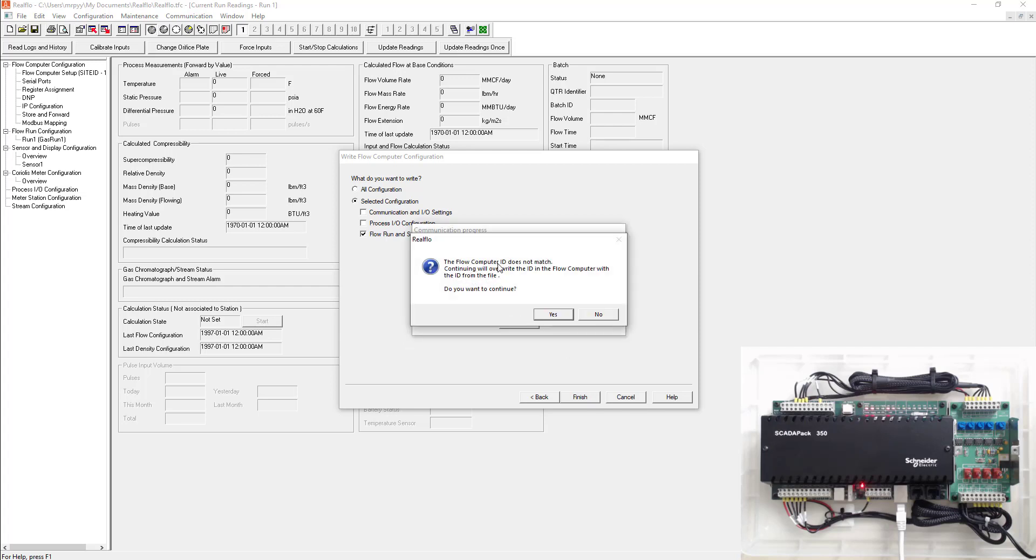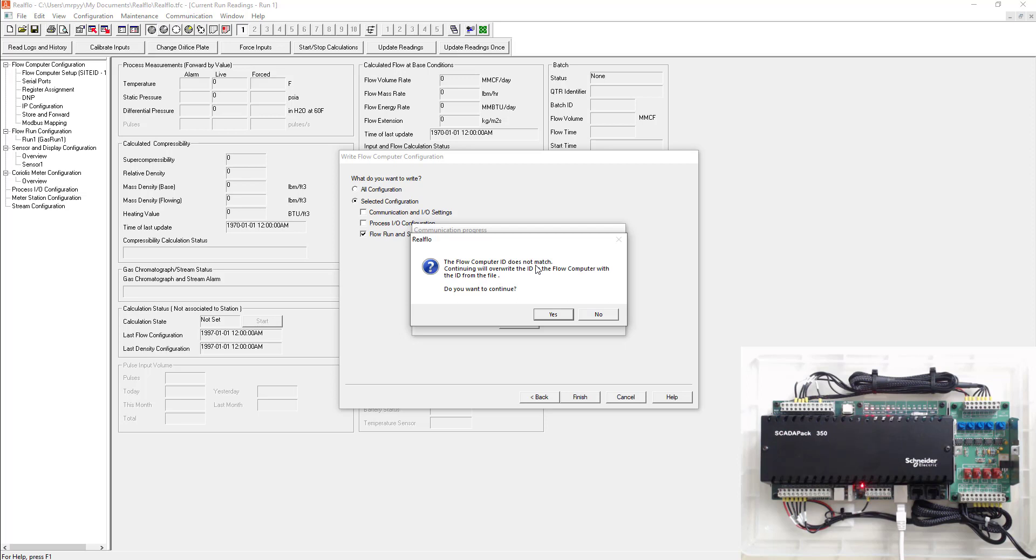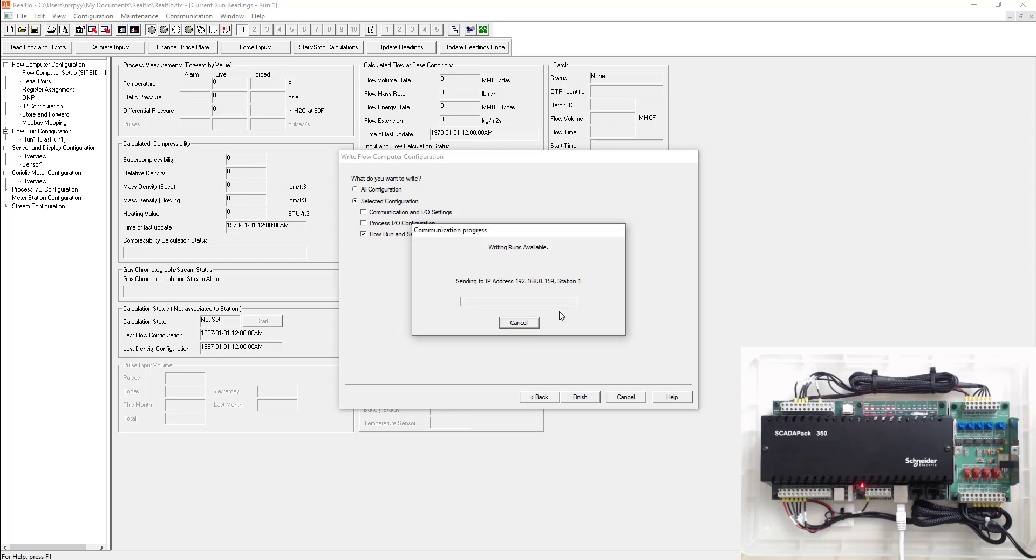It says the flow computer ID doesn't match. So that was that site ID name that we gave to our configuration. It doesn't match what's currently in the SCADA pack because what's in the SCADA pack is just the default, whatever gets written when you initially write the C program in. So this might be an issue if you were going to a site and you thought you had the right config and you went to hit write and the site ID or the flow computer ID doesn't match, then clearly your configuration is completely different than what's in there. But for this application, we want to select yes. So it's writing everything at this point.